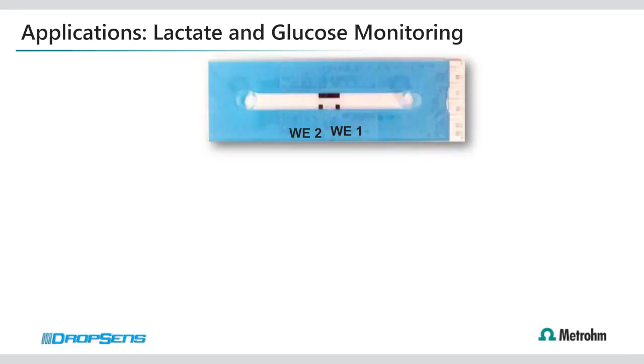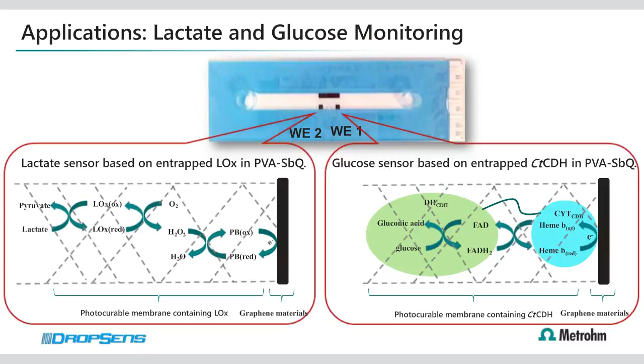Next is an example of working under flow conditions with a dual graphene working electrode. Each electrode is modified with 2 different enzymes, allowing the detection of lactate and glucose respectively in each of these working electrodes. The experimental setup is really simple. The flow injection system consists of a peristaltic pump supplying continuously buffer solution through the electrochemical cell. The sample is directly injected through a septum and the electrochemical detection is carried out.